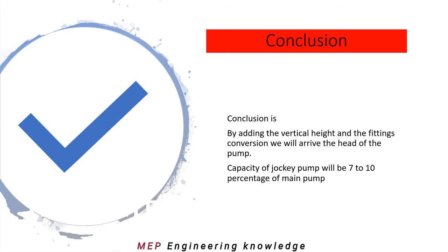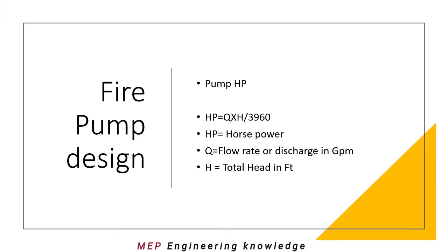In conclusion, by adding the vertical height and the fittings conversion we arrive at the head of the pump. This is applicable for all sprinkler and hydrant pumps. The capacity of the jockey pump will be 7 to 10 percent of the main pump capacity — this is the industry standard. After finding the discharge and head of the pump, we need to find the HP of the pump, that is, the horsepower.